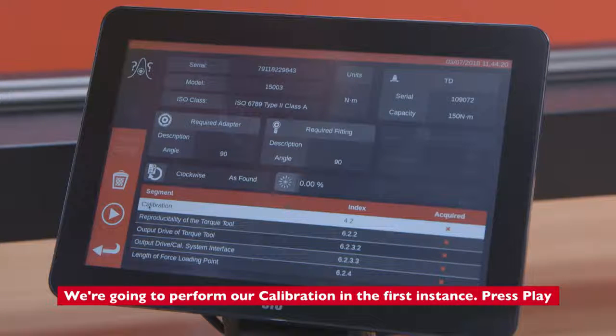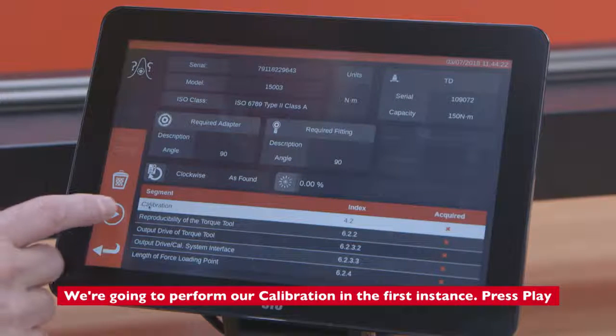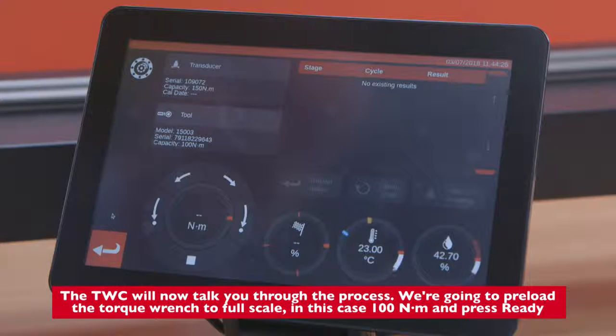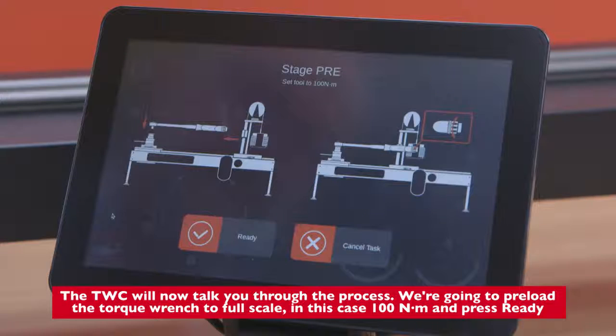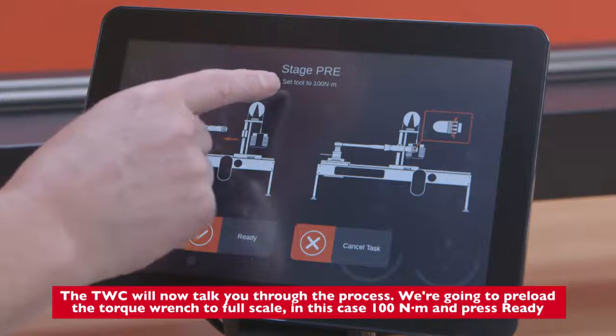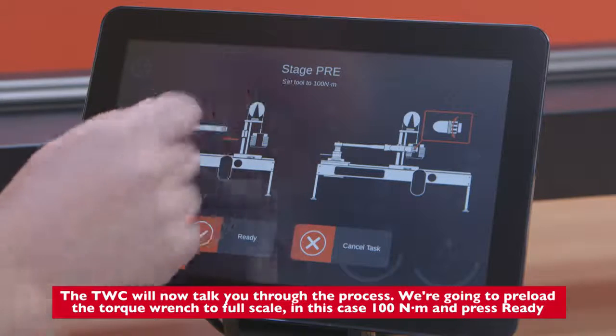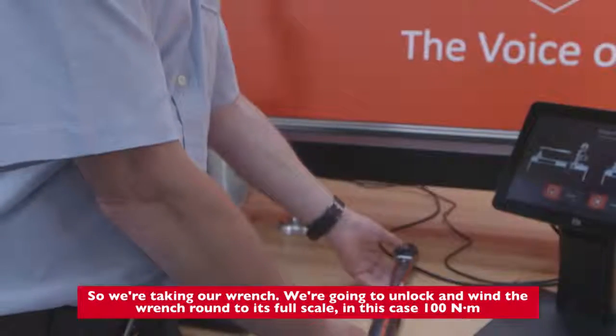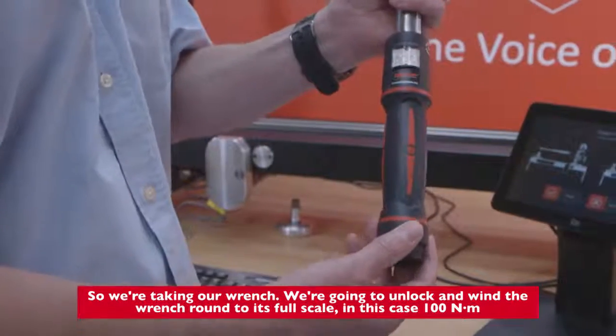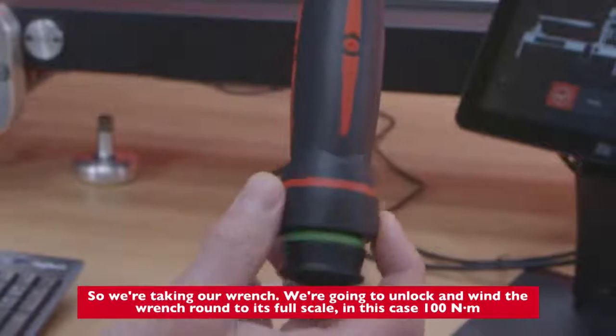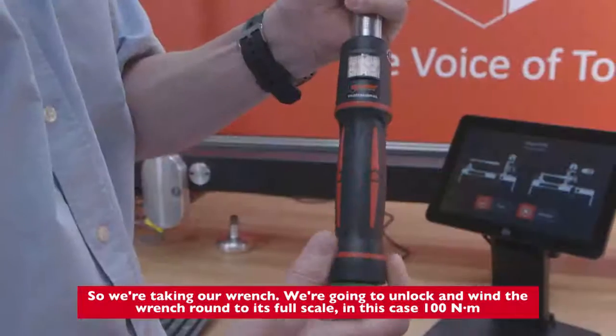We're going to perform our calibration in the first instance. Press play. The TWC will now talk you through the process. We're going to preload the torque wrench to full scale, in this case 100 Newton meters, and press ready. So we're taking our wrench, we're going to unlock and wind the wrench around to its full scale, in this case 100 Newton meters.